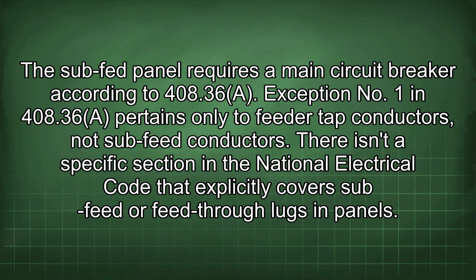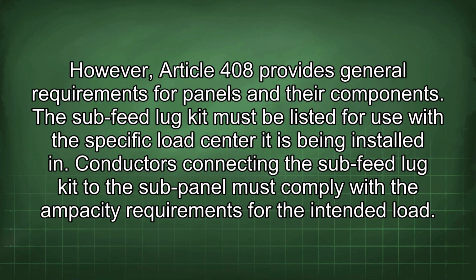Exception No. 1 in 408.36 pertains only to feeder tap conductors, not sub-feed conductors. There isn't a specific section in the National Electrical Code that explicitly covers sub-feed or feed-through lugs in panels. However, Article 408 provides general requirements for panels and their components.